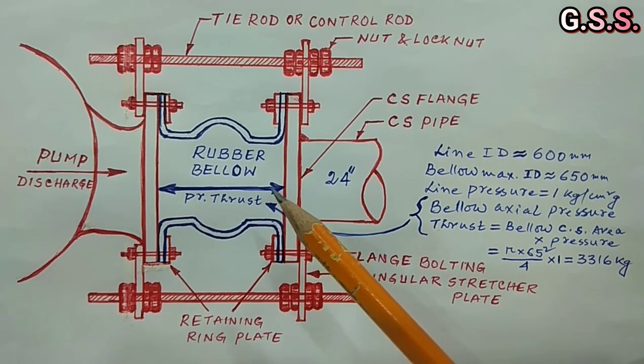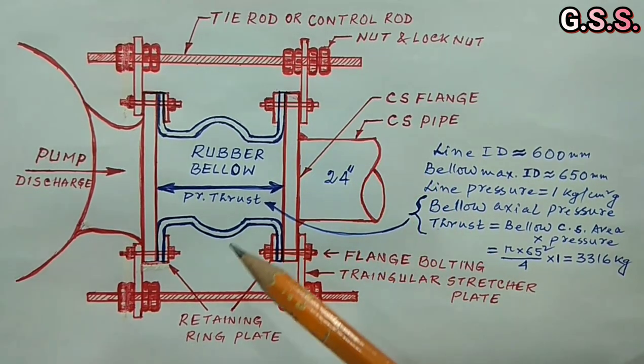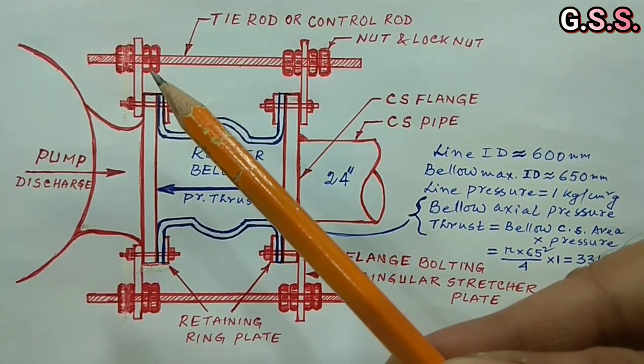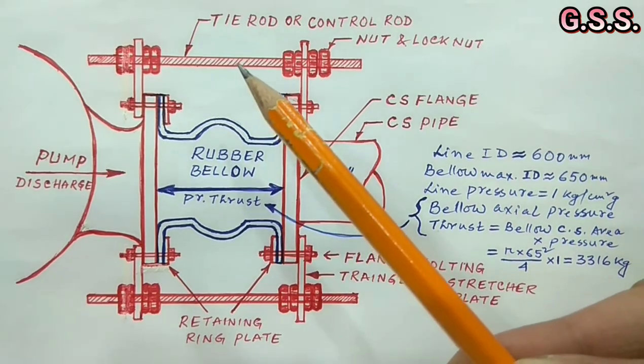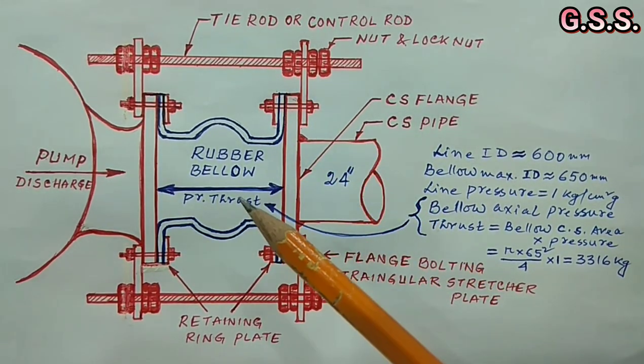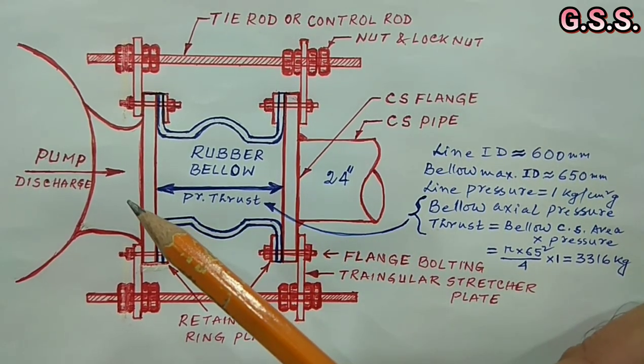But since two tie rods are kept tight with nuts and lock nuts, this pressure thrust will be absorbed by these two tie rods and no load will be transmitted to piping system or to connected pump nozzle.